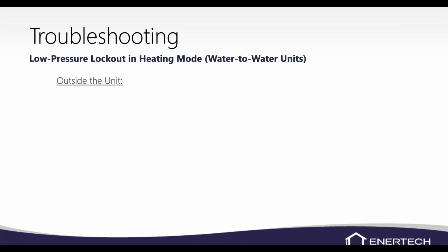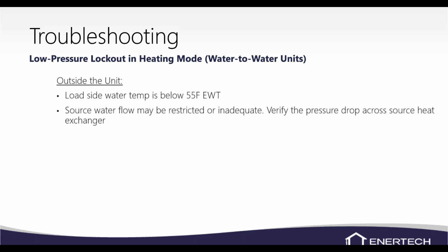Low pressure lockout in heating mode on a water-to-water unit, that would be the source side of things. So we're going to look at your water temperature below 55 degrees on your load side could do it too. So if you're coming from cooling to heating mode and your tank is cold, you may have to jumper the low pressure on the unit and get it above that temperature, because we could run some low pressures with that low load water temperature. Source water flow is restricted or inadequate. It could be froze up too. So if you don't have proper antifreeze in your load side, or your source side, then it could be freezing up prematurely and not getting water flow.